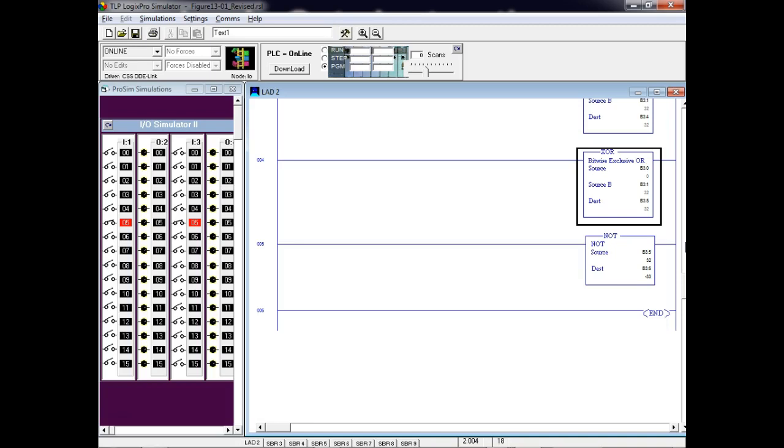What do we do with an exclusive OR? We compare two 16-bit words to see if they are equal. Now the problem with our exclusive ORs and exclusive NORs, when we use contacts, we can only use 2. And if I wanted to compare 16 bits, it would take 16 rungs, right? You understand?